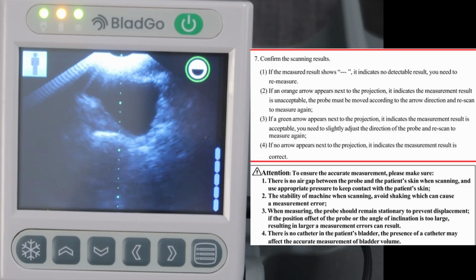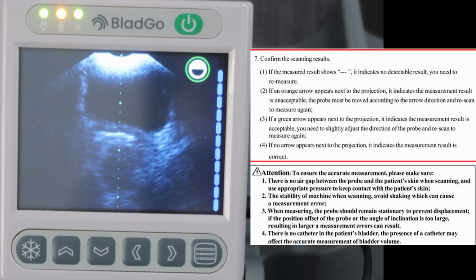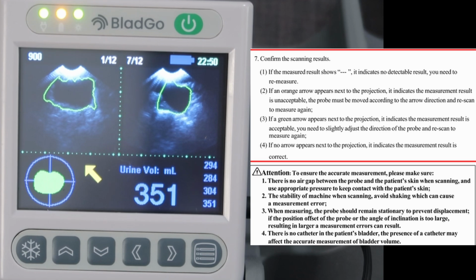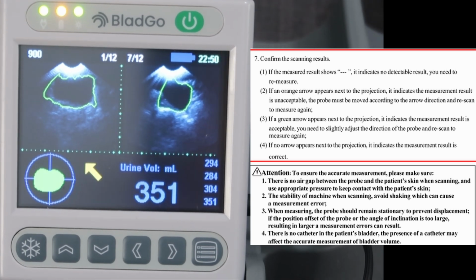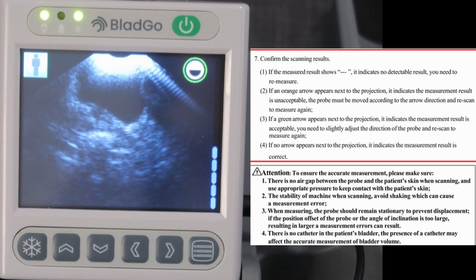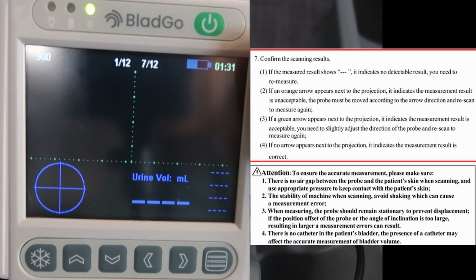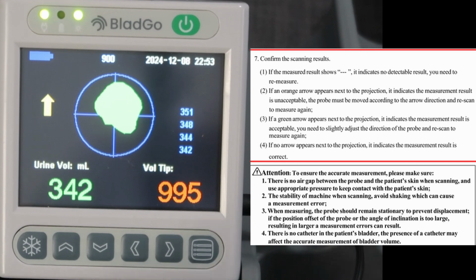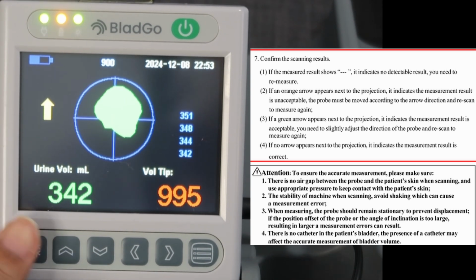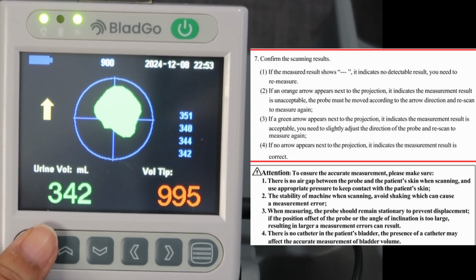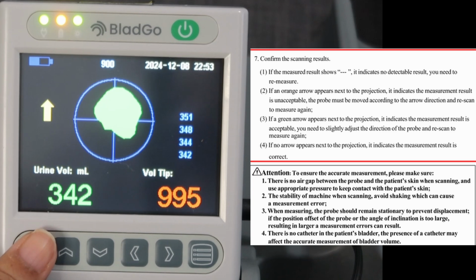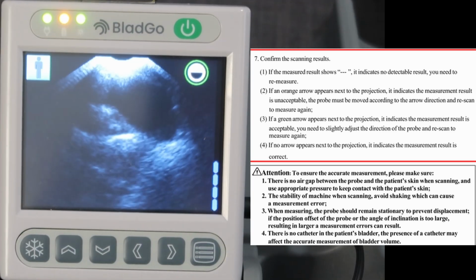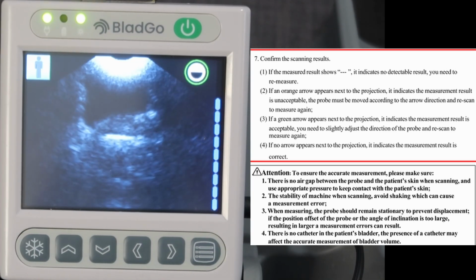Here is an example of what an inaccurate scan would look like. So you can see on the screen here, we have this orange arrow, and I'm going to read from the manual what that means. It says if the measured result shows these dashes, then there's no detectable result at all and you need to remeasure. If an orange arrow appears next to the projection, it indicates that the measurement result is unacceptable. The probe must be moved according to the arrow direction and rescanned to measure it again.